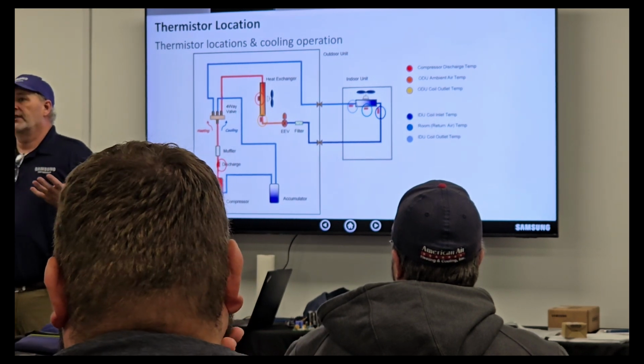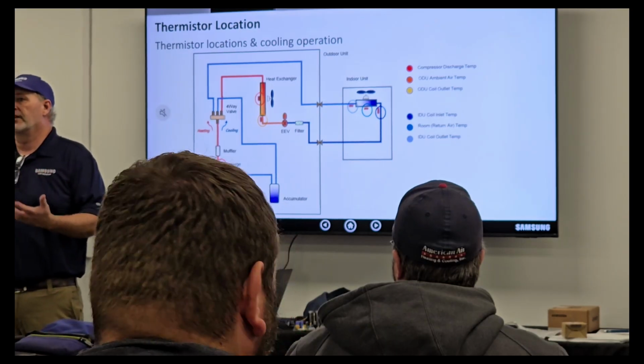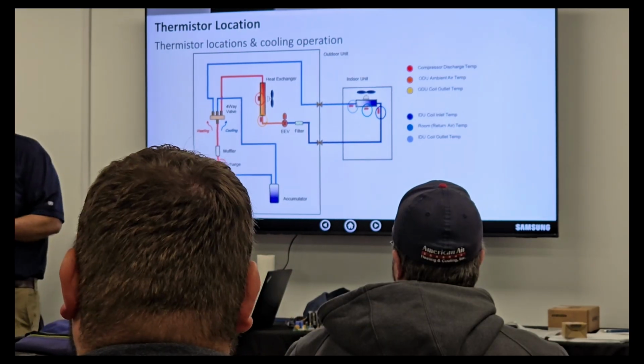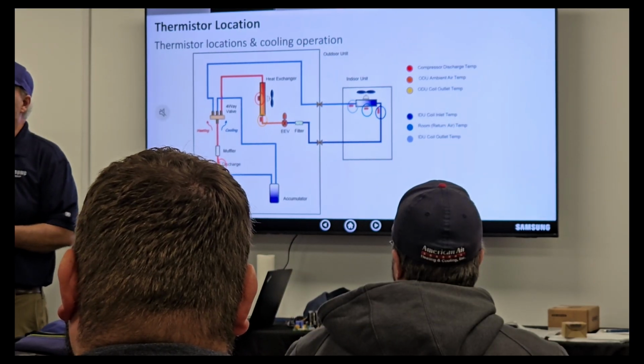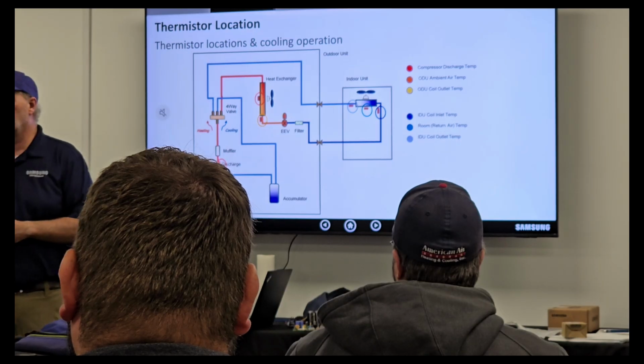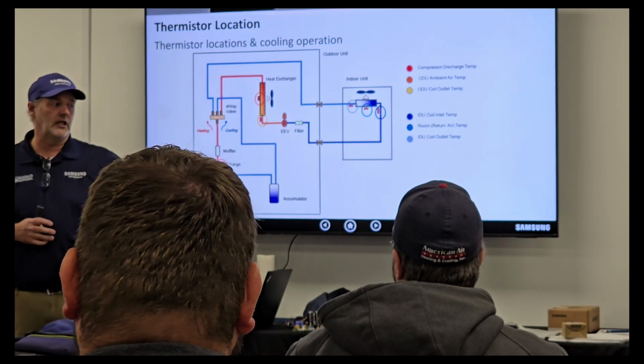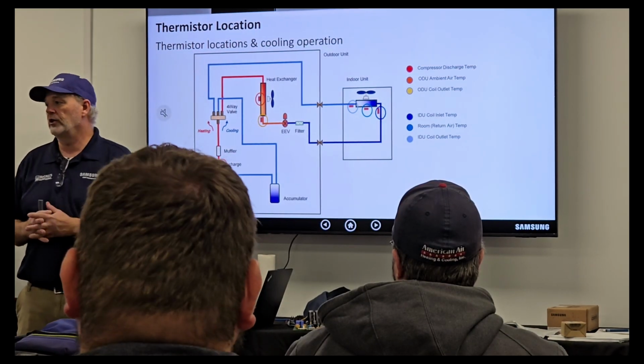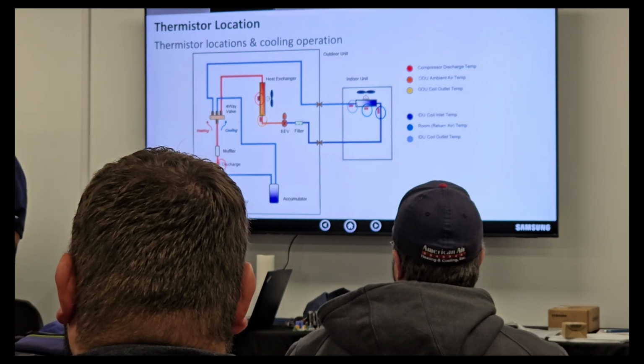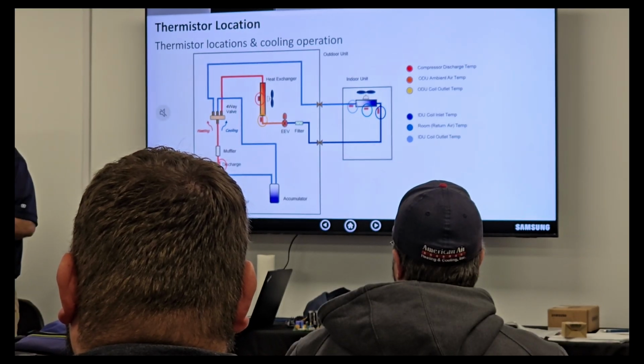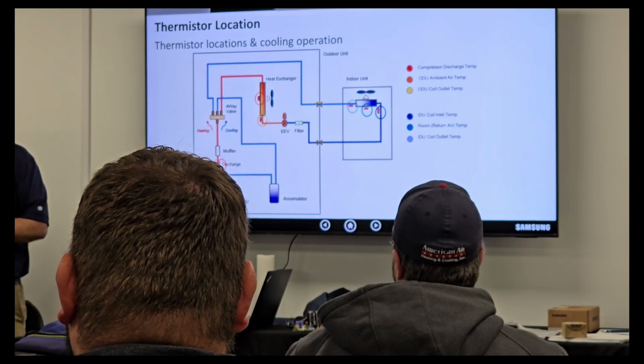So ultimately, what we're doing sometimes is detrimental. One of those things is brazing. Not so much with R22 because mineral oil doesn't give us that problem. But when we start using PVE or POE oil, guess what we do with all that debris if it's on the inside of that pipe? We clean that pipe, we scrape it off. So now it goes into our system.